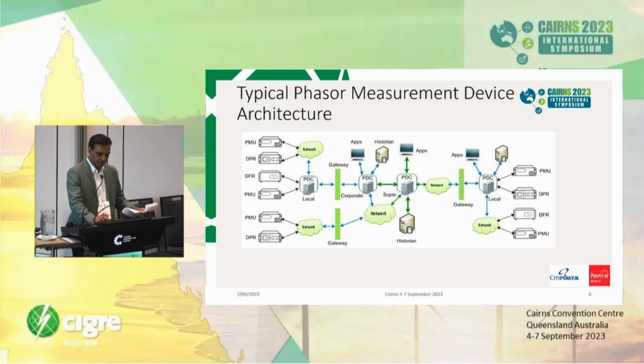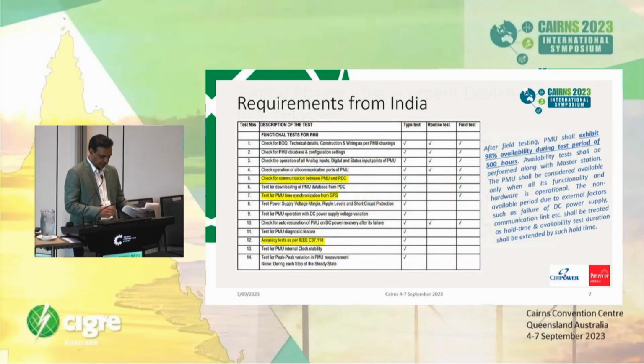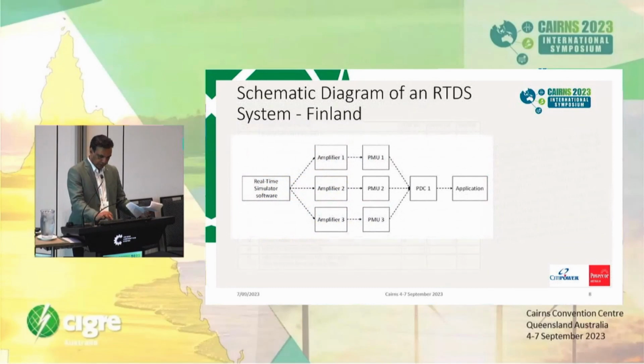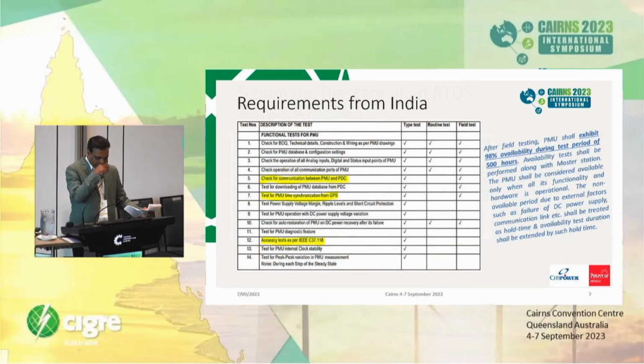The first example I'll be taking is from India. This was a specification for a project called URTDSM, which, to my knowledge, is the largest project in the world, with more than 3,000 PMUs sending data to the control center. If you look at the right-hand side, it says that after field testing, the PMU shall exhibit 98% availability during a test period of 500 hours.